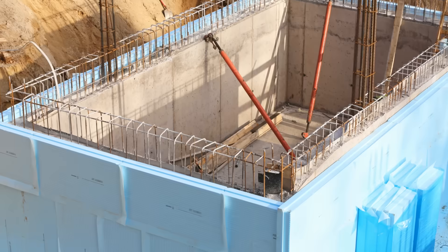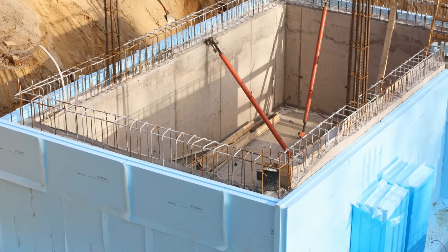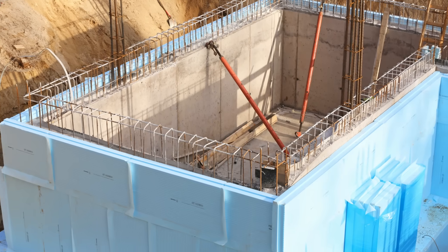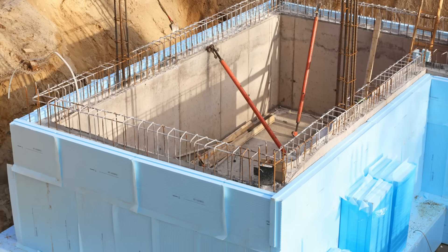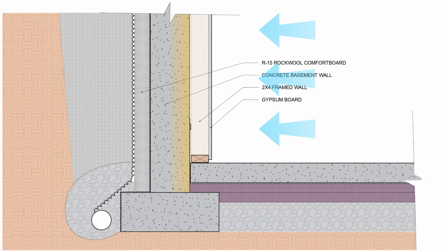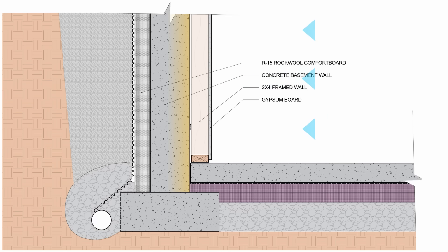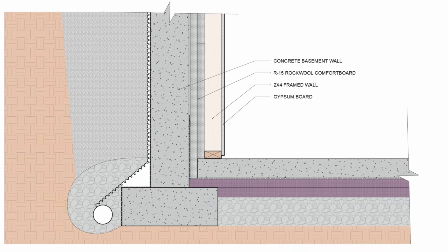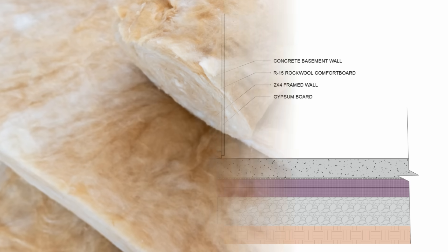If we install this continuous insulation layer on the outside of the basement wall assembly, air permeability and vapor permeability would not matter. We essentially have a perfect wall where the structure is kept at interior conditions, the water and air control layer is on the outside in the form of the waterproofing, and it's not thermally isolated. However, if we push that continuous insulation layer to the interior side, that concrete wall no longer is thermally coupled to the interior — it's cold and remains relatively cold throughout the year.